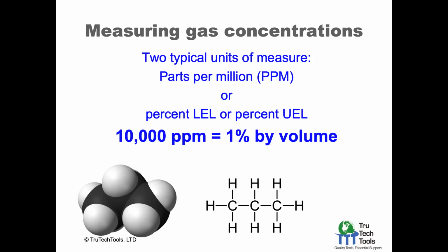That's another way of measuring just what is the concentration, what's the mixture, how much sugar is in the iced tea. That's what ppm tells you, that's what percent by volume tells you. But the fact with the upper and lower explosive limit, that is more about the type of gas that you actually have. So parts per million is just purely concentration. It's just a ratio of what gas you have to the rest of the available air. Whereas the percent LEL or percent UEL relates to the type of gas. It's the characteristic of the gas. And we'll be talking about two main gases here, methane and also propane.